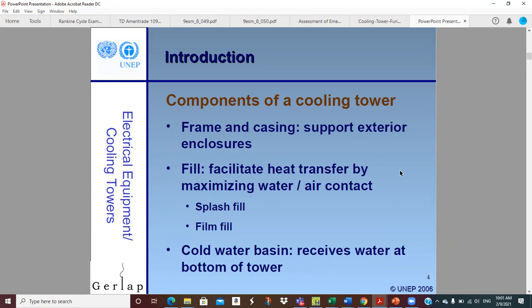The fill, there's actually different types of fill. When we get further into this, there's a slide or two that gives some numbers, some characteristics of the fill, and they actually list a third type of fill. But the standard, or the old time, was splash fill. In the old days, they used to make that fill out of some sort of exotic wood. I think it was like teak and stuff from over there in the rainforest that wouldn't deteriorate because it's sitting there wet all the time. There used to just be these little slats. They kind of stack them in this pattern to have lots of gaps in there, and the water would splash down on top of it and break up into smaller droplets.